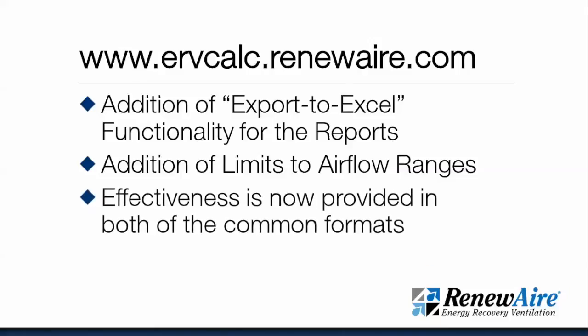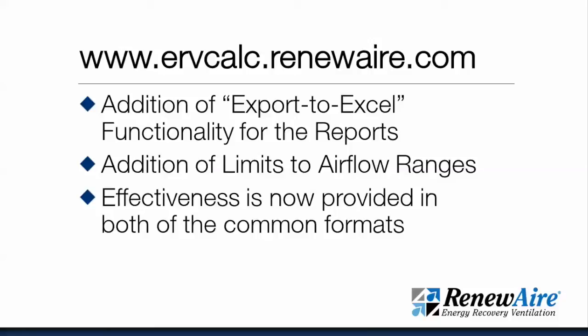The effectiveness is now provided in two common formats. The formats are going to be defined by both ASHRAE 84, the method of testing for energy recovery ventilators, as well as ASHRAE 90.1, the energy efficiency standard. There's differences between those two calculation methods that both have important impacts to the building and now we're going to display both of those formats going forward.